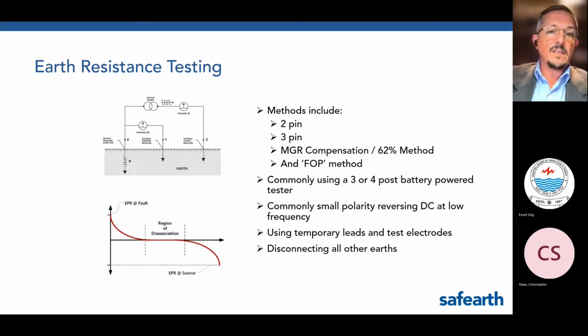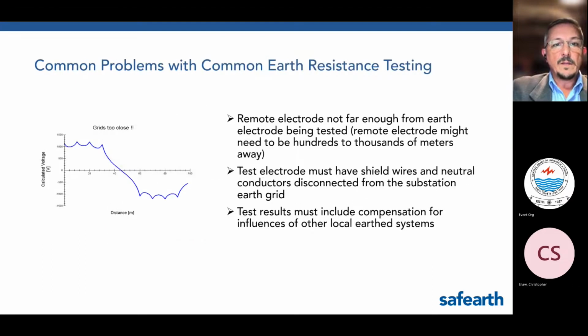There are limiting factors as to when this test will be helpful and when it will be substantially misleading. Here's some of the common problems explained. Even if this test is used to only provide a grid resistance, there are many complications with the test that can impact the validity of the results. For example, if the remote electrode is not far enough from the ground electrode being tested, which may need to be hundreds or even thousands of meters away, the actual grid resistance would not be at the midpoint, and it may not even be at what's called the MGR compensation point of 62%. Also, it's reliant on electrodes being similar in magnitude and similar in physical size, which is only true for smaller earthing systems and for the higher resistances.